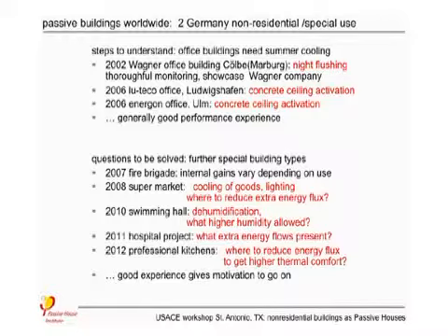The Wagner office building has a night flushing for cooling. In German climate, in summertime, during night it's so cool the air temperature goes down below 18 degrees centigrade, so just by opening windows you can cool. They did it with the Wagner office. I will not show you that in detail because of time.